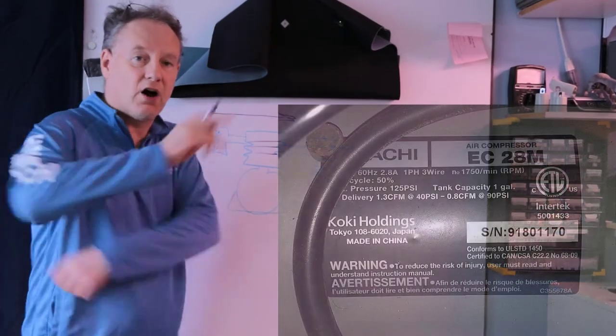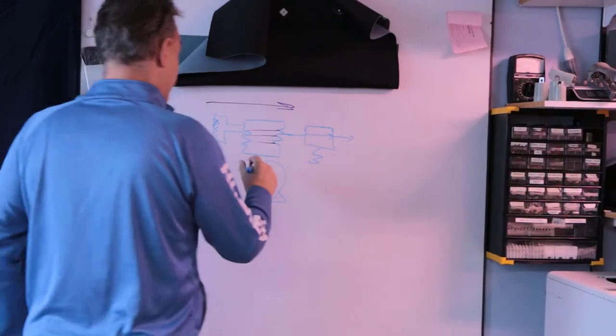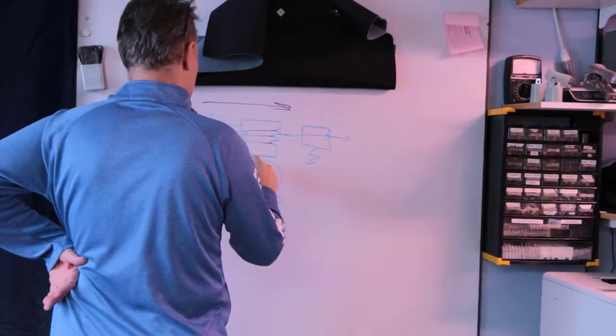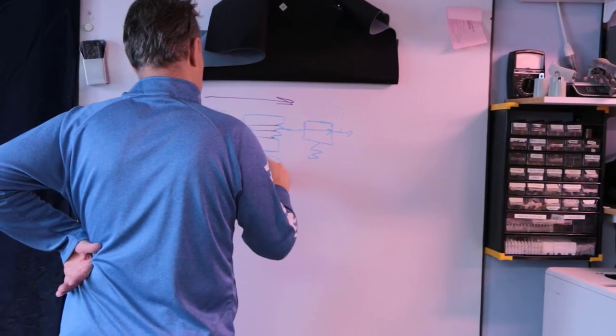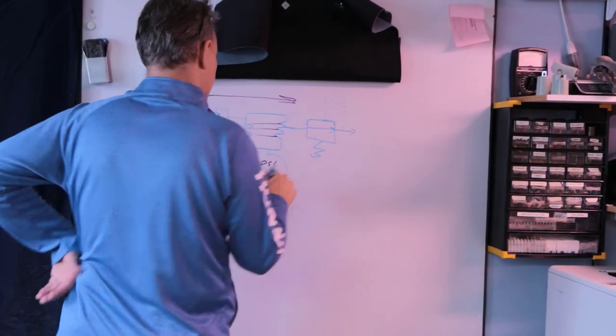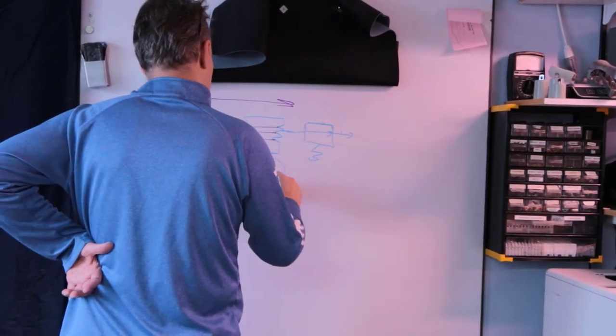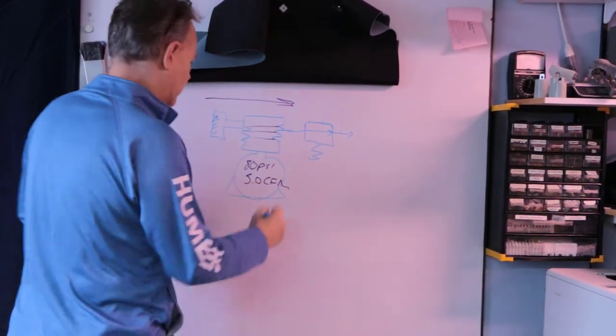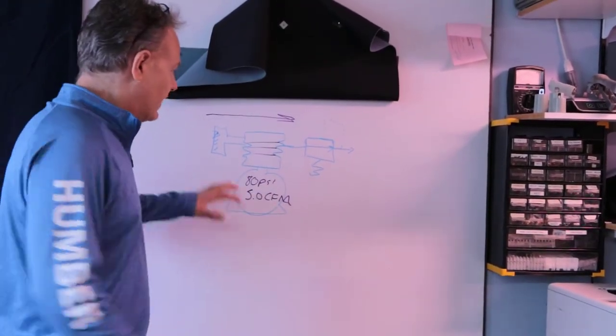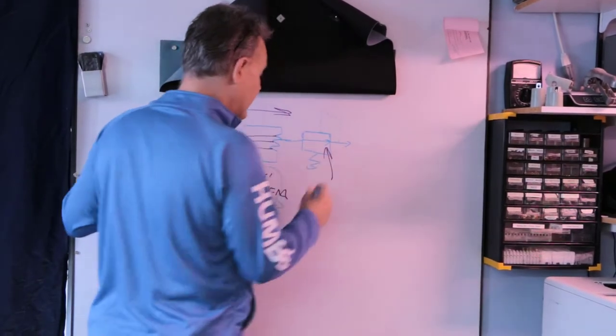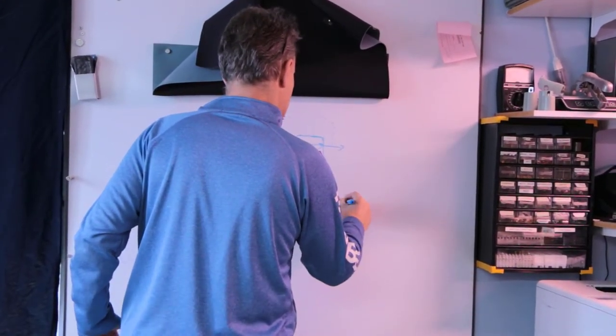Compressors are rated somewhere, and often they'll have two different ratings. I'm going to work with one of them. On the compressor, it says if this thing is set to 80 PSI — which is gauge pressure — it will give me five cubic feet per minute of pressurized air. So if I set this pressure regulator to 80 PSI, the flow rate coming out is going to be five cubic feet per minute.